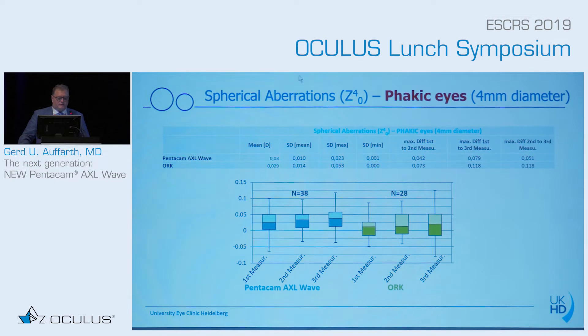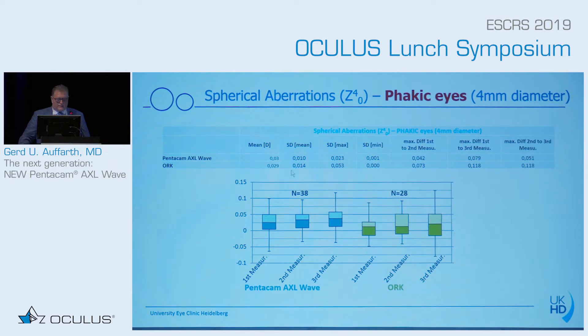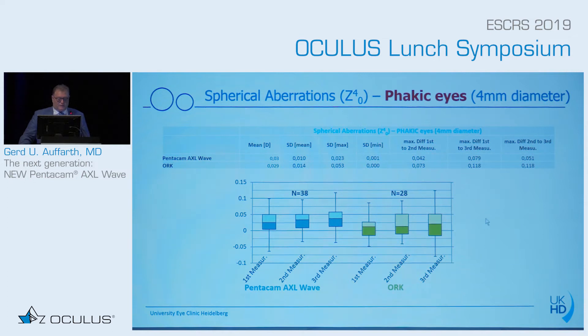Looking at spherical aberration in phakic eyes, here is a comparison between the Pentacam and the Schwind wavefront analyzer. You can see the first, second, and third measurements with the Pentacam AXL, and here with the Schwind device — they measure more or less exactly the same. Standard deviation is similar in both machines, a little bit better with the Pentacam. The difference between first and second, first and third, and second and third measurements is much smaller in the Pentacam AXL compared to the Schwind device.